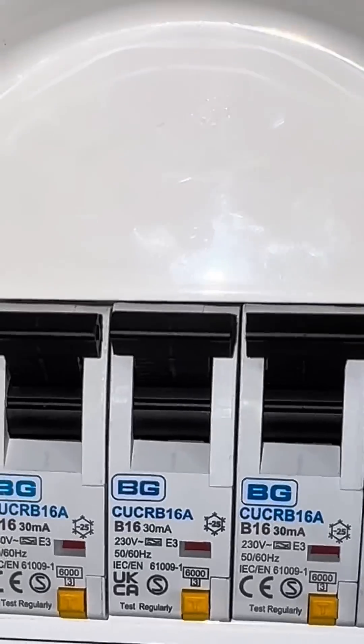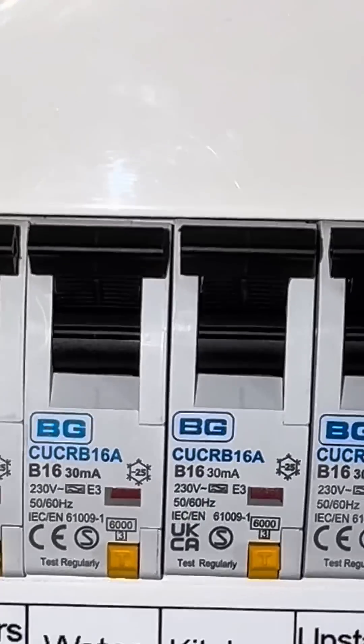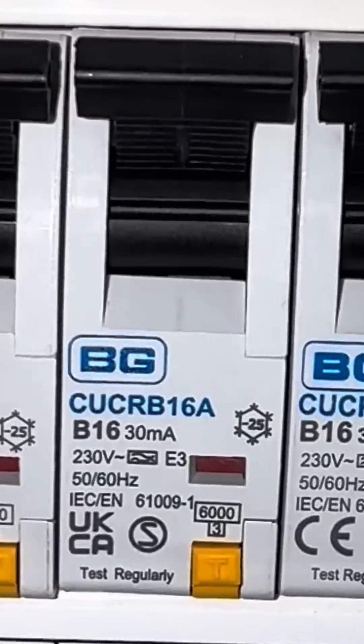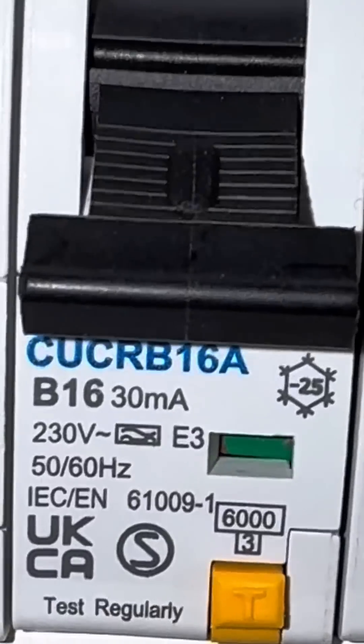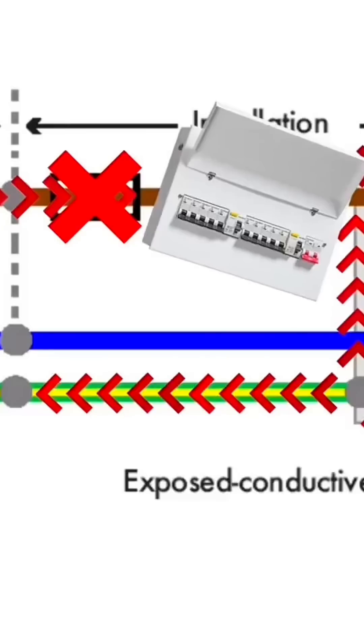The fault current will pass through the main cutout fuse rated at either 100, 80, or 60 amps but will not cause operation. The fuse that will operate is the one closest to the fault. In this case, the fuse located within the consumer's unit will operate, clearing the fault in circuit.